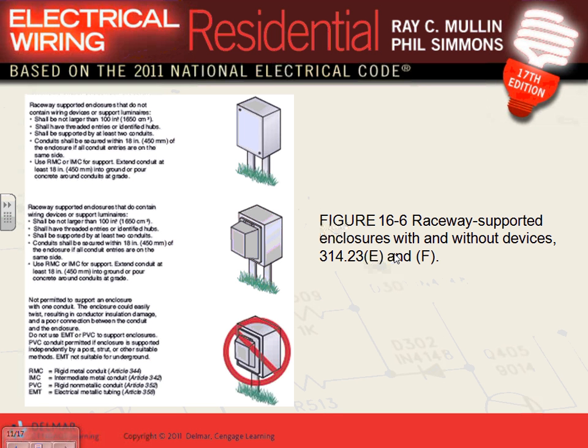This one is really good, guys. This sheet will tell you how big of a box you can support from conduit. You can see them if you walk downtown Minneapolis and Hennepin. You see this PVC conduit coming from the bottom and supporting boxes. How big of a box you can support from a conduit, not from a wall. You're not supporting from a wall or a structure, but from a conduit. If you read through it, it has to be 100 cubic inches or less. The ones that you can support, and not larger. So these boxes cannot be larger than 100 cubic inches. So you're not going to fit a big box and support it from a conduit, number one. And you need two conduits over here, threaded or with a hub, when you support them.